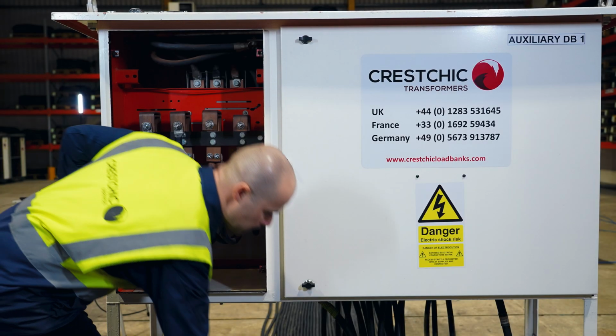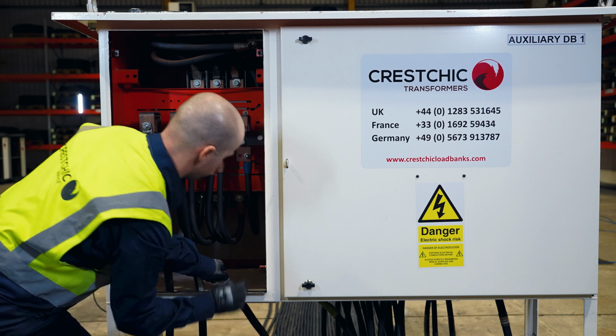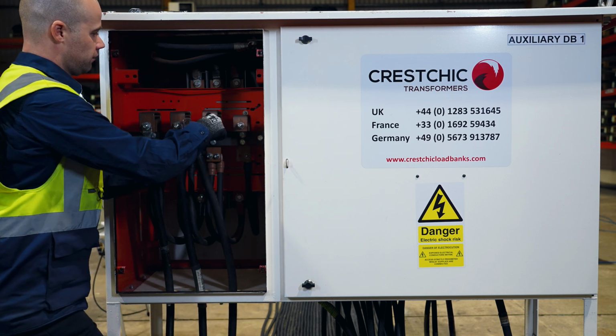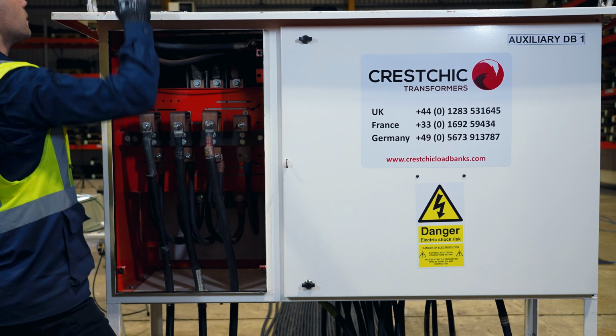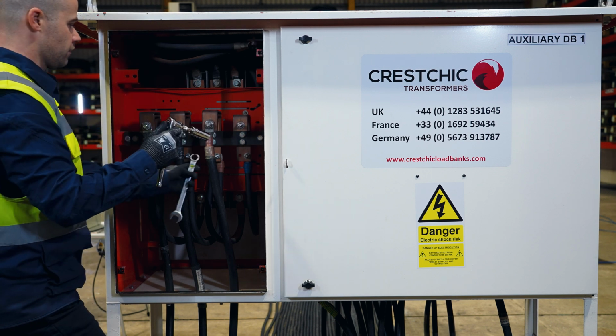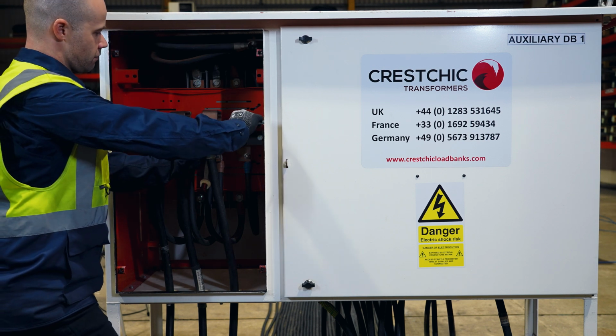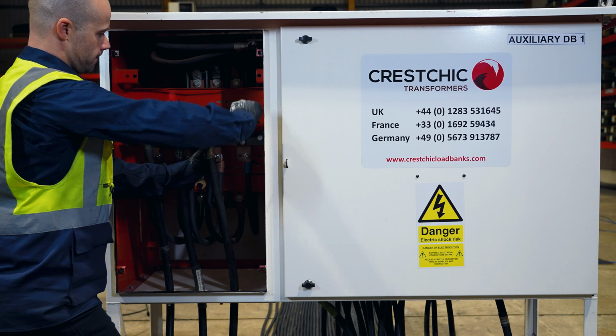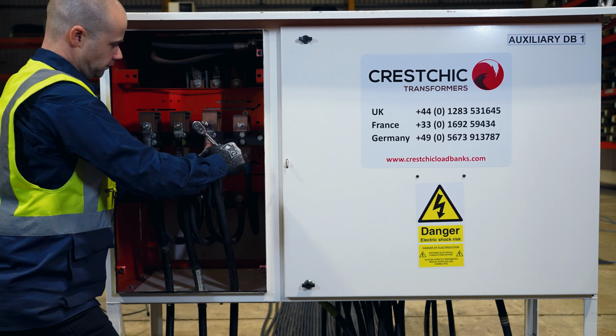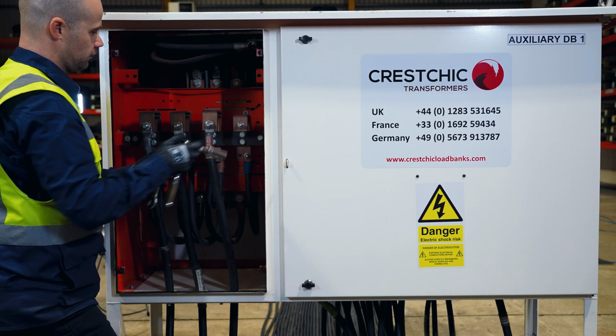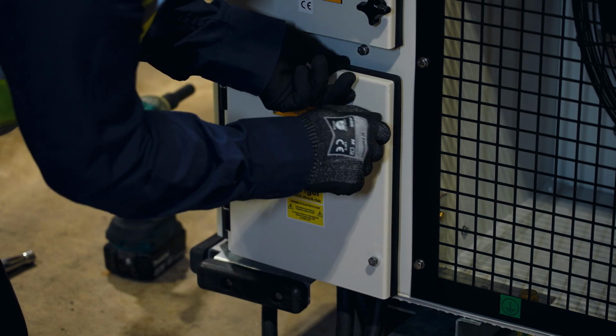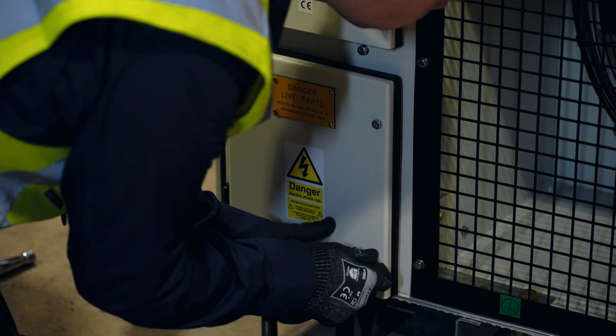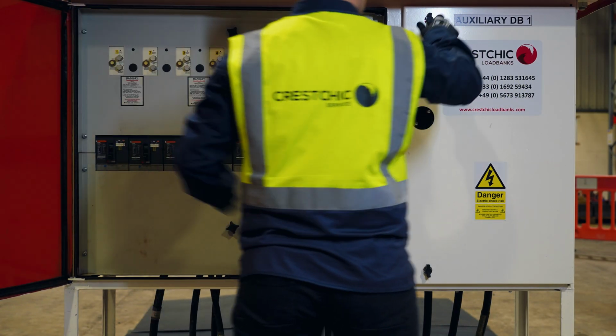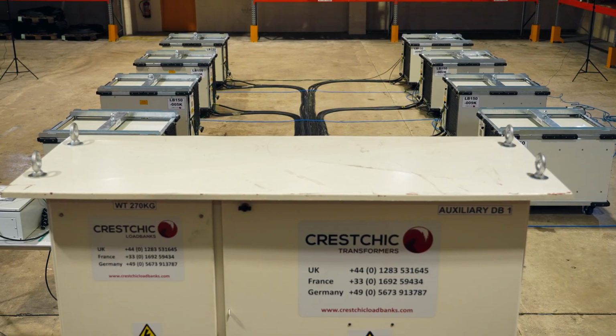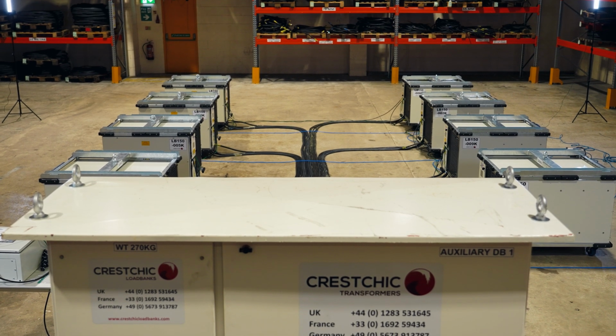The load cables from the load banks can either be directly connected to the supply source or a distribution panel. Load cables should always be directly connected from the load bank to the source supply or distribution panel. The load bank terminal connection should never be used to distribute cables to other load banks. Once connections are made to the load bank, panel doors should be fully closed. A circuit breaker with protection settings should be used between the supply source and the load banks. This should be set according to the maximum load required.